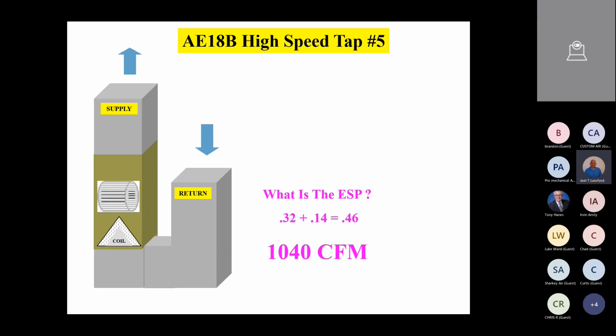Man, give yourself a star. That's close enough. I had 1,040. That's close enough, because it's kind of falling in between there. So what you're doing is you're kind of extrapolating a little bit. I had 1,040 at 0.46, but if you had 1,050 or 1,053, that's close enough. Because remember, team, if you're within 10 or 15 CFM from the chart, you're close enough.